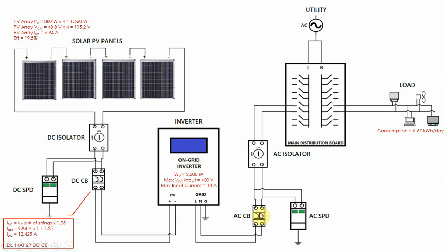Next we determine the AC circuit breaker at the output of our inverter. We calculate this by taking the maximum power rating of the inverter — 2,200 watts — and dividing by the grid voltage of 220 volts AC. Our minimum circuit breaker should be 10 amps. If a 10-amp circuit breaker is available, go ahead and use it, but for this example we choose the next available rating: a 12-ampere, 2-pole AC circuit breaker.